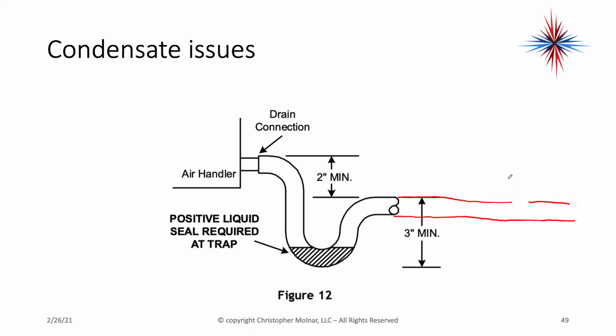Now, if you think there might be a separate trap someplace in the system, you're going to come out of this trap, okay, and you're going to put an air break tee, which is basically just a tee with a standing pipe in here, okay, that goes over the height of my air handler drain connection. Okay, it's just a T with an open pipe. What this does is allow an air break so you don't have a double trap situation. A double trap situation can back up water in here. A lot of installers use that excuse as the reason they do not install a trap at the air handler. Always install a trap at the air handler with an air break if you have any doubt about proper pitch or anything else like that.